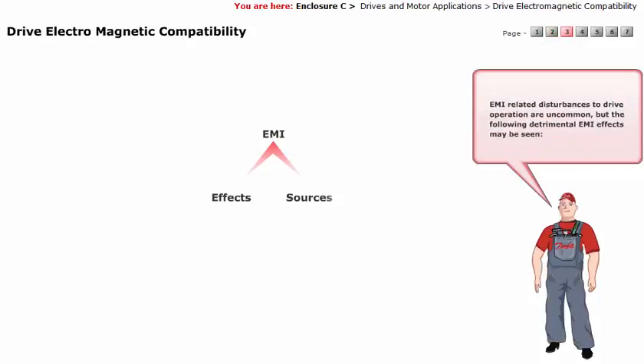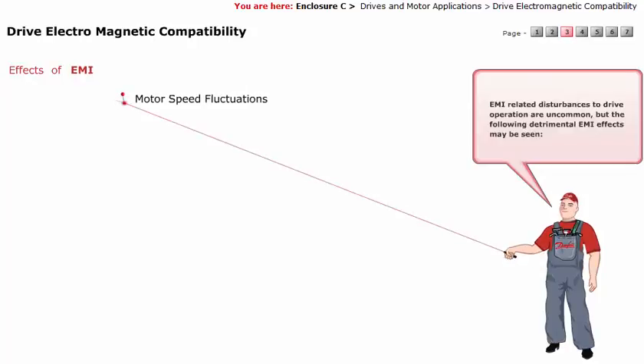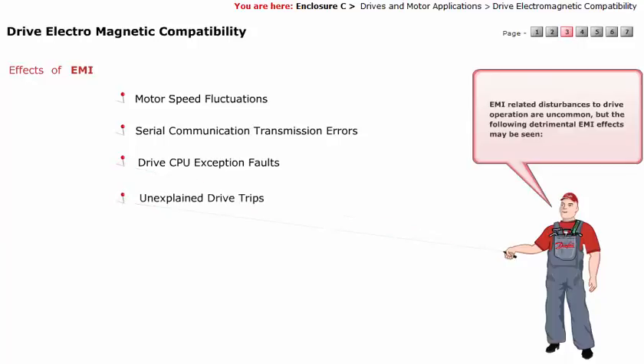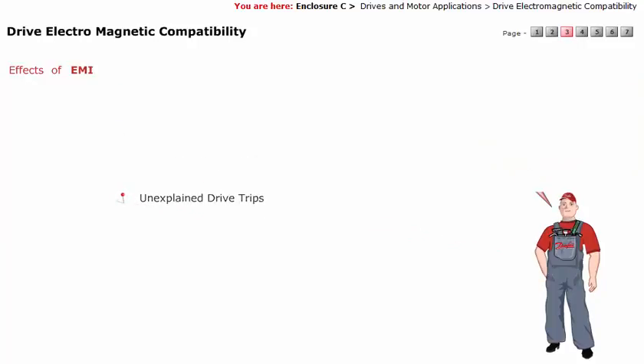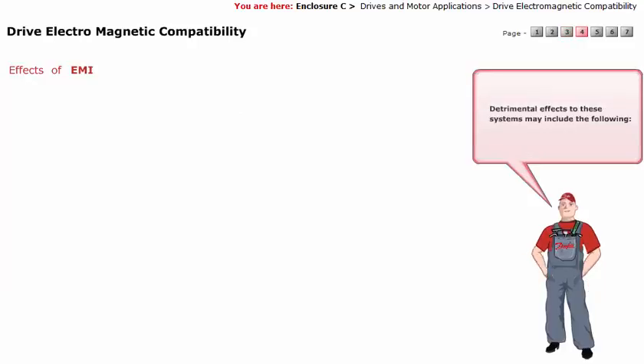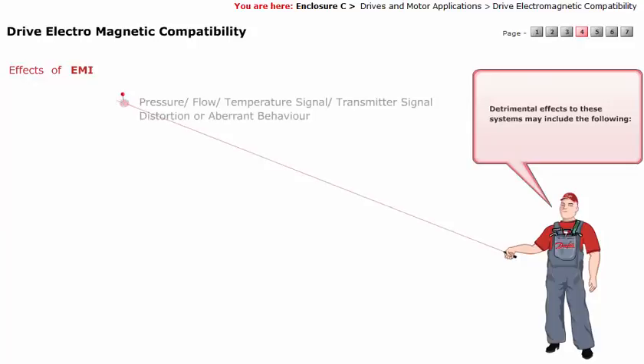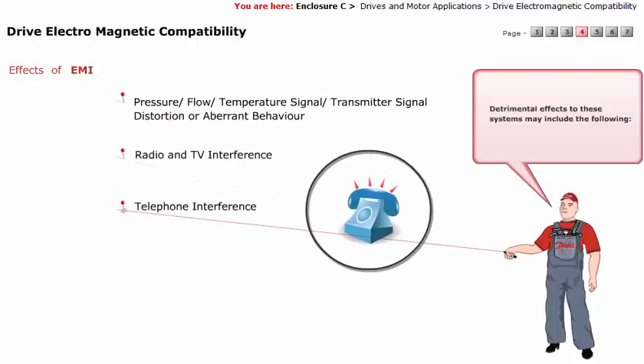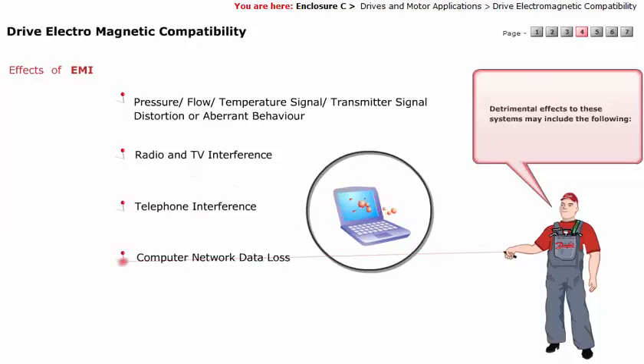EMI-related disturbances to drive operation are uncommon, but the following detrimental EMI effects may be seen: motor speed fluctuations, serial communication transmission errors, drive CPU exception faults, and unexplained drive trips. Detrimental effects to other systems may include pressure, flow, and temperature signal transmitter distortion, radio and TV interference, telephone interference, computer network data loss, and digital control system faults.